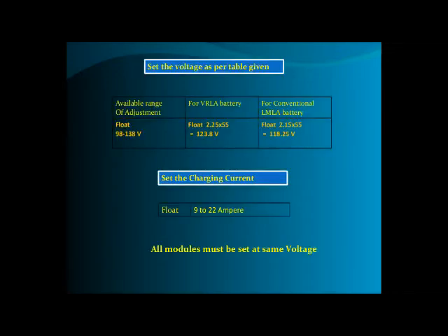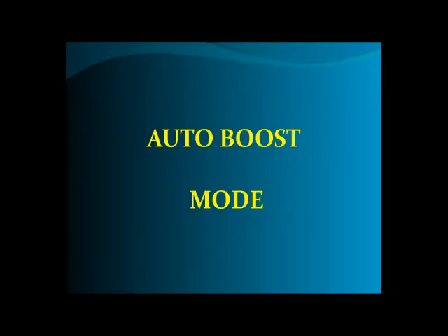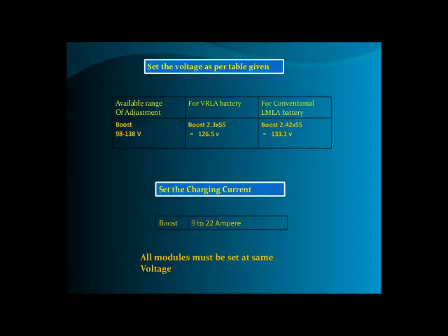The mains input AC supply as well as the battery bank is connected to this module as mains AC and DC source of input supply. In auto float mode, the float voltage and boost voltage of each rectifier module shall be set as given in the following tables.